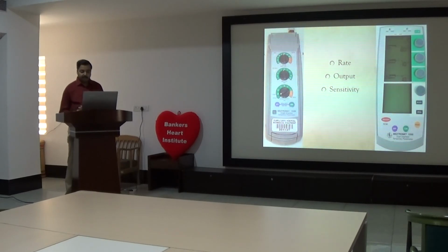There is one more function over here, asynchronous mode. This also we will discuss, but asynchronous mode means the pacemaker will not sense anything. The pacemaker will continue pacing at the rate whatever you have set. Say if you have set it at 80, forget the patient's rate, the pacemaker will pace at 80. Even if the patient's rate goes beyond 80, the pacemaker will try to pace it. So that is asynchronous mode. Very rarely it is required.